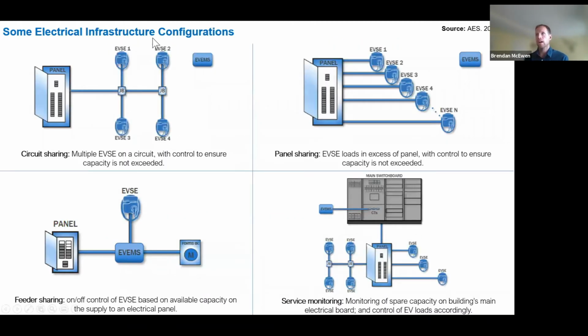So there's a range of different types of EV energy management systems and technologies and associated electrical configurations that they can enable. These are some of these different electrical configurations. A common and fairly simple form of energy management would be here in the top left, circuit sharing. Here, across a branch circuit, in this case, we've got 4 charging stations sharing that branch circuit, and they adjust their consumption so they don't exceed the capacity of that branch circuit. Now you can also overload a panel and do the management at the panel level.